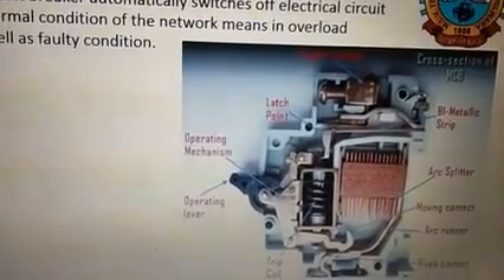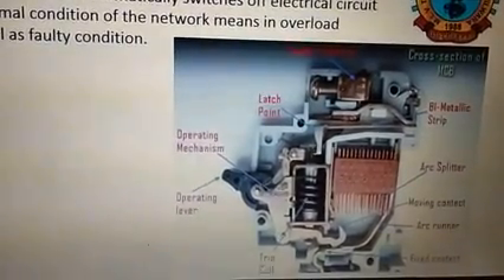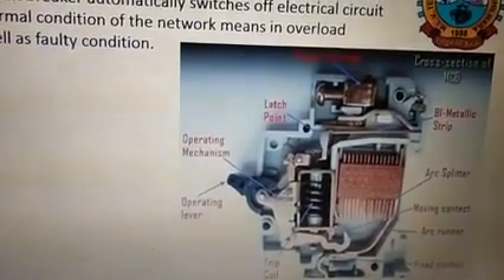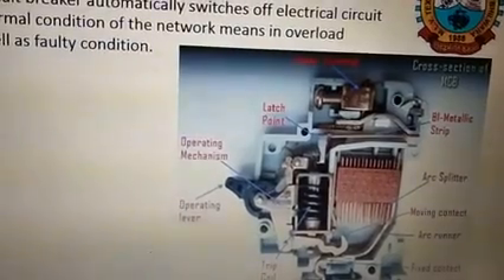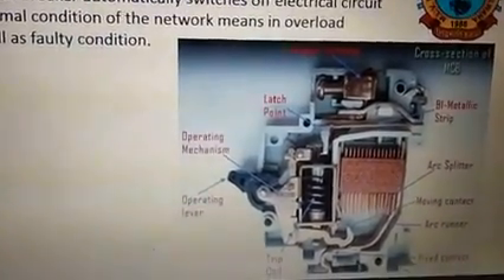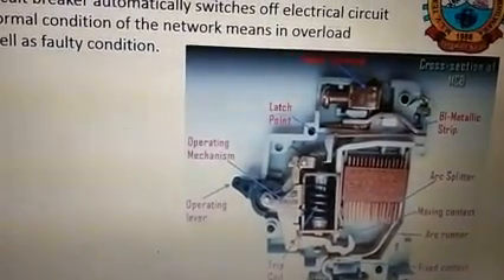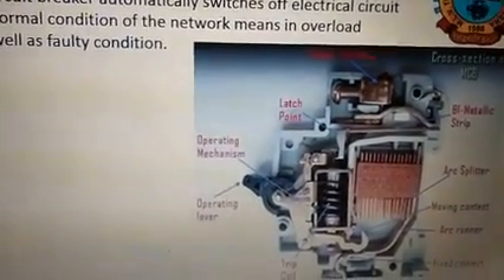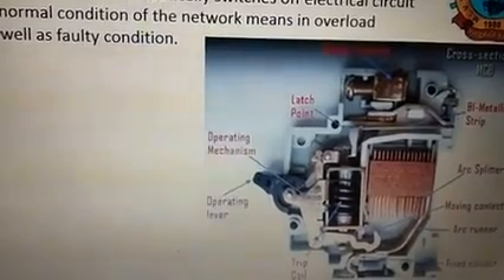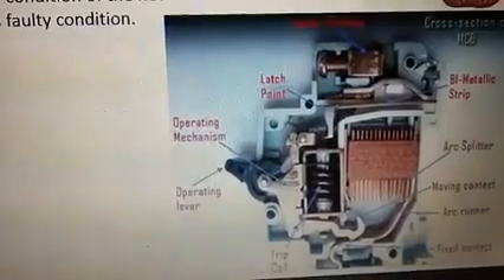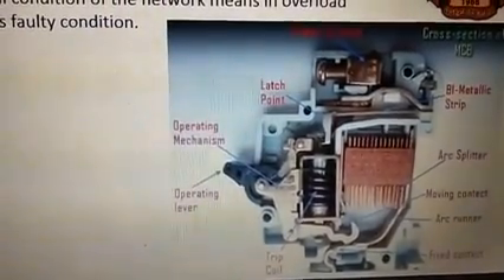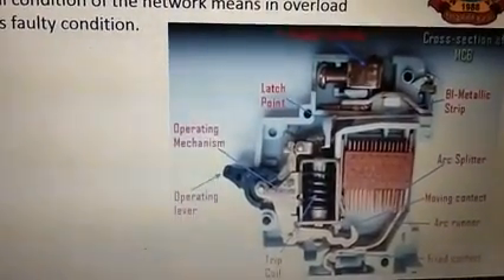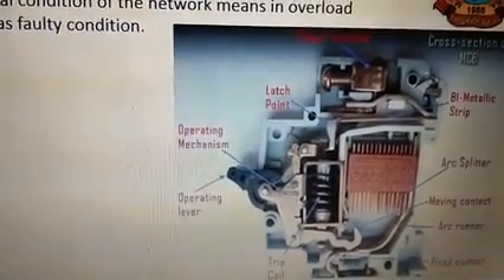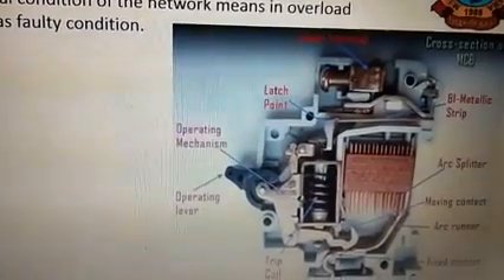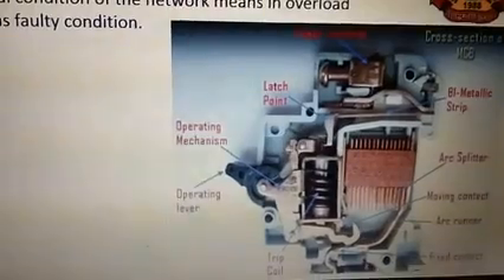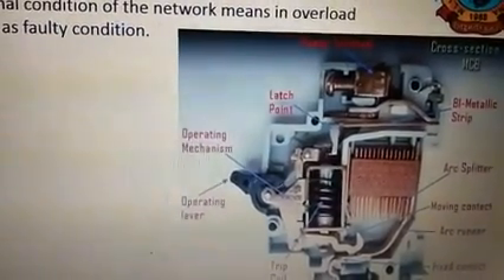There is no automatic mechanism to turn on the MCB. It is going to be turned off automatically by the bimetallic strip through the latch point, but once it is turned off, it must be turned on manually. This mechanism protects from the faults arising due to overcurrent or overload. MCB construction is very simple, robust and maintenance free. Generally, an MCB is not repaired or maintained. It is just replaced by a new one when required.